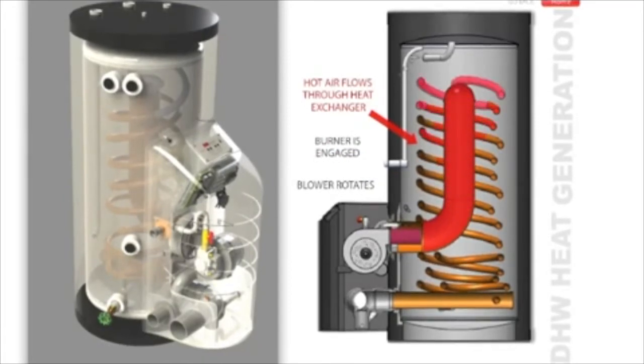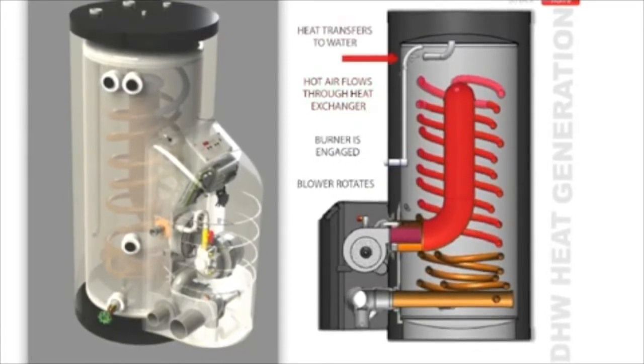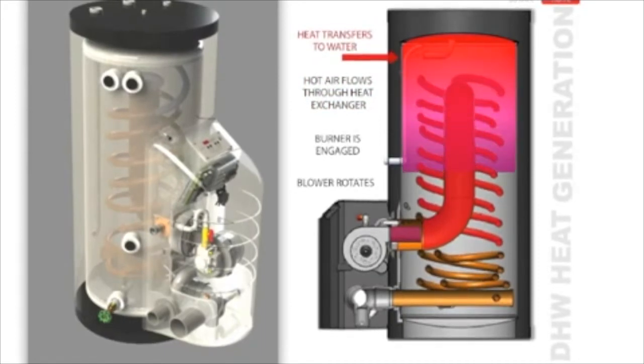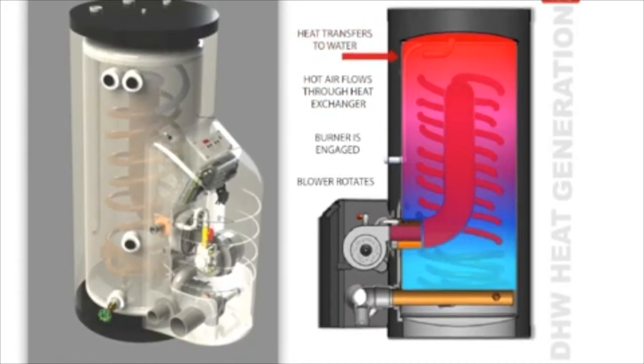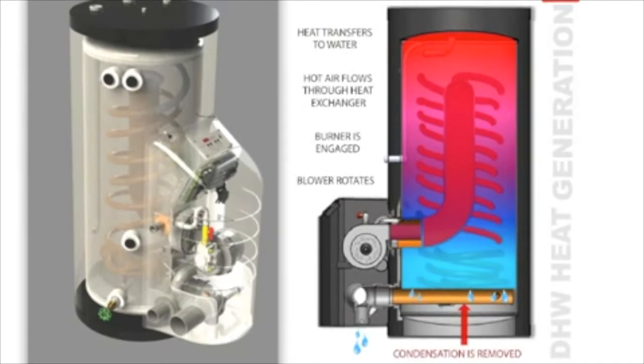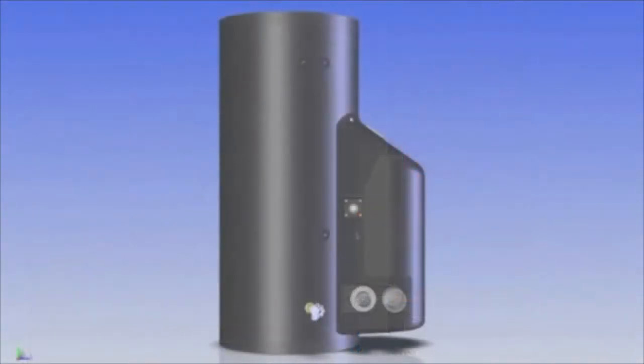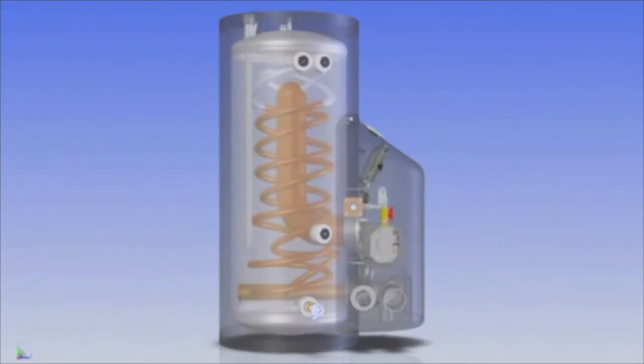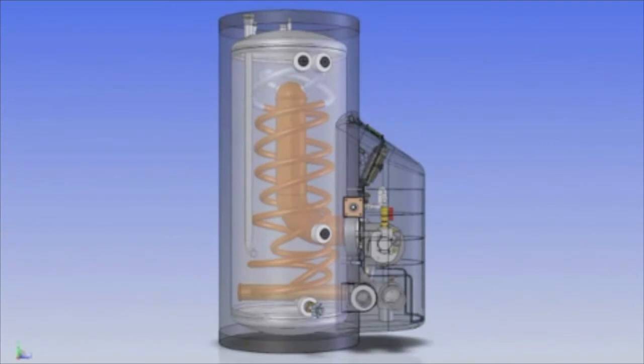Backed by over 20 years of superior performance, HTP's proprietary heat exchanger receives flue gas from the combustion chamber up a 5-inch diameter cupronickel core to a header where it reverses direction and continues back down through multiple stainless steel and cupronickel spiraling tubes before exiting the unit.